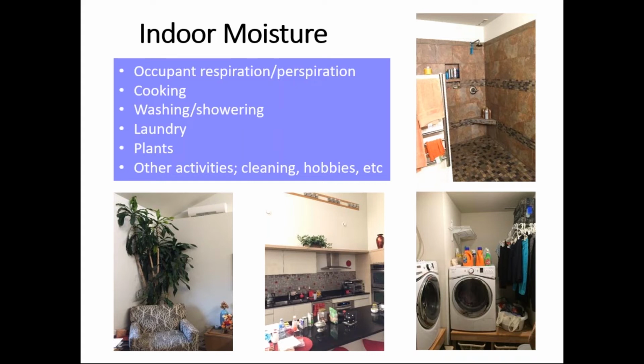The bathroom in the upper corner, similarly, because of the way the ventilation system operates, that we exhaust from the bathroom and continuously moving air through in one of the modes of operation for the system that we have in place, the bathroom fully dries out. Towels, washcloths, as we'll discuss, they fully dry out. There's no hints, indication, discoloration of any mold or mildew in this bathroom. And so the type of ventilation we'll be discussing, it works. And this is from firsthand knowledge of it working.